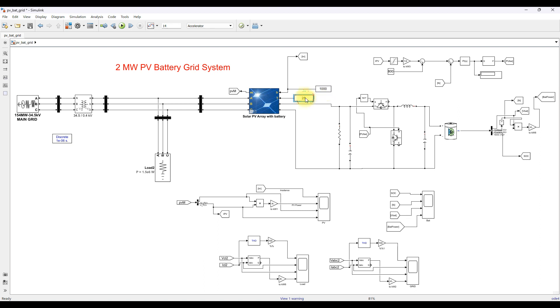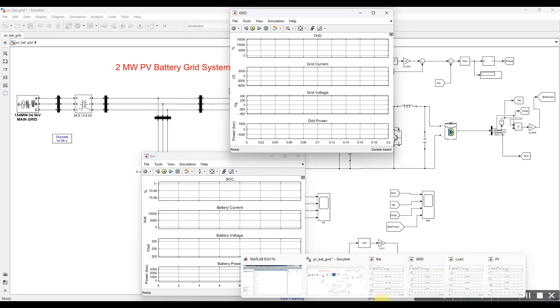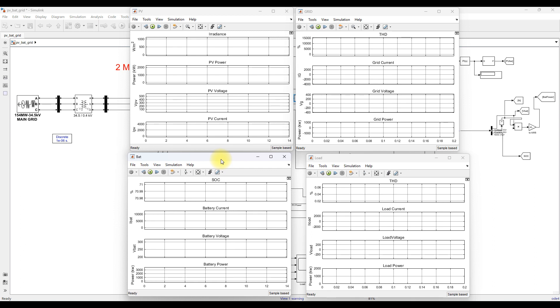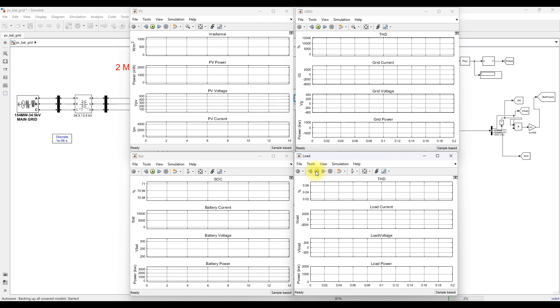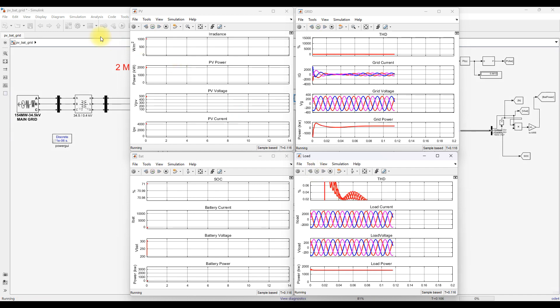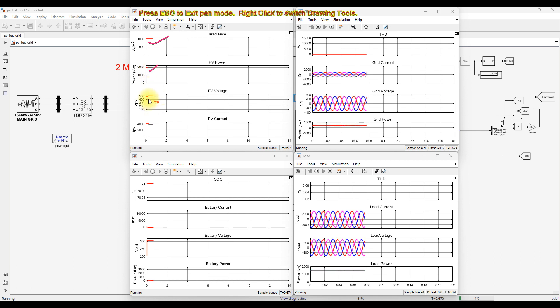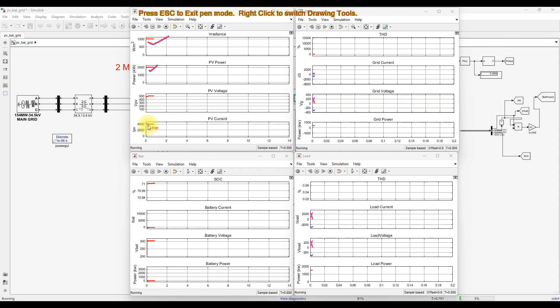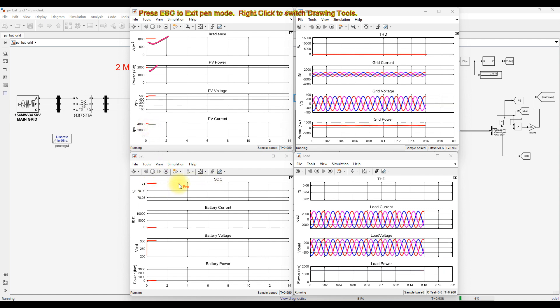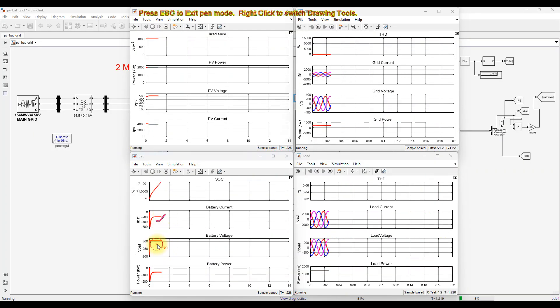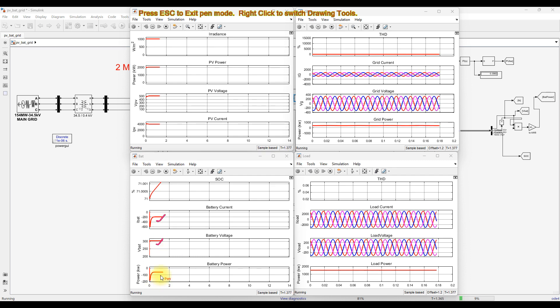Now operating the system with irradiation of 1000 watts per meter square and temperature of 25 degrees Celsius. PV is generating around 2 megawatt — shown as 2000 kilowatt. PV voltage is around 500 volt and PV current is around 4000 amps. The SOC keeps increasing, battery current is minus 200 amps, battery voltage is around 305 to 310 volt, and battery power is around minus 60 kilowatt, indicating the battery is in charging mode.